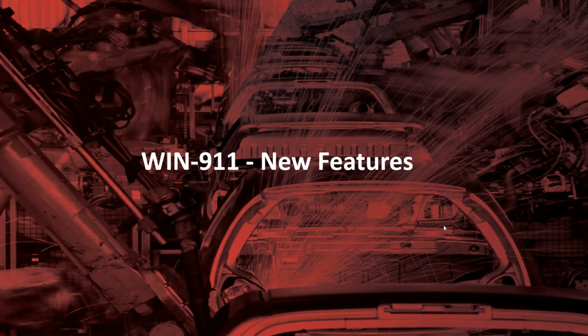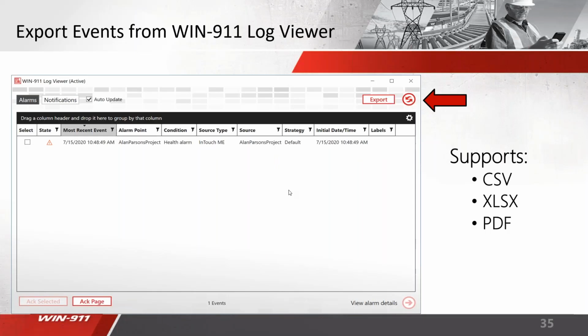All right, so now we're going to get into some new features of 4.20.13. And the first thing we're going to mention is exporting from the log viewer. And we put a little button up here where you can export. Unfortunately, I don't have a screenshot, but I'll show you the demo later. You can always do your historical data by unchecking the auto update here. Once you do that, you're going to see a date range option. So you could pick what date range you want to see your alarms from. Once you have that, you click the export and you'll have a choice to save it as a CSV or Excel file or PDF.